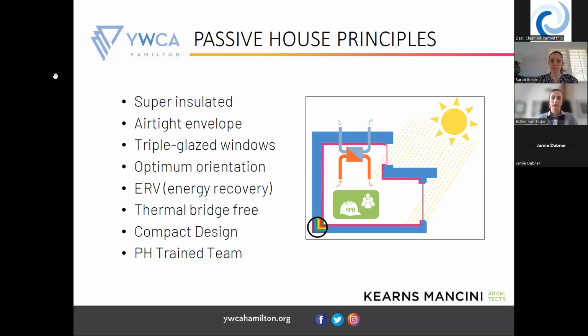What's shown in orange and gray there is what we call energy recovery ventilators, or you also get heat recovery ventilators. What we used at the Y specifically was an ERV, so that captures the moisture as well as the heat in the building. It essentially captures what we can reuse instead of just pumping it back out to the outside.